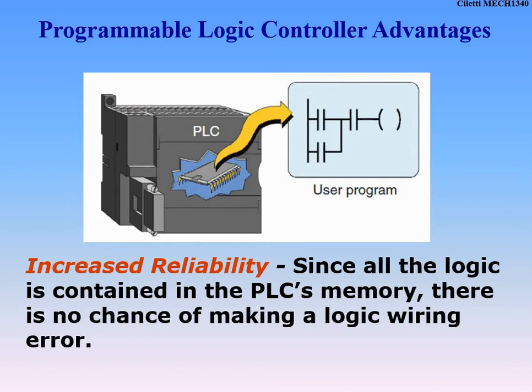What's good about PLCs is their increased reliability. They do not crash and reset like Windows. They're very, very reliable. All the logic is contained in the PLC's memory, so there's no chance of making wiring errors. Once a PLC is running and operating, it's not going to go wrong. When something breaks, it's not because of the PLC — it won't randomly change the program or get a virus. There might be a wiring issue in the field, and we can use the PLC to determine what's not working, helping us troubleshoot the system.